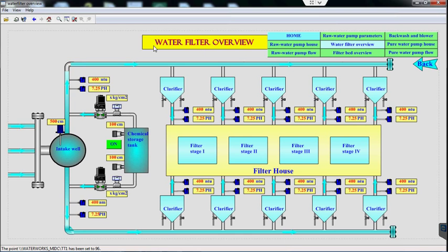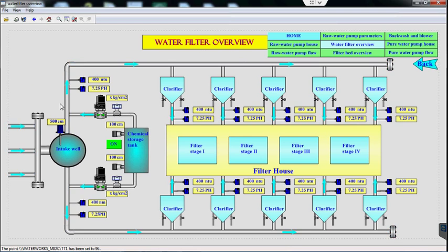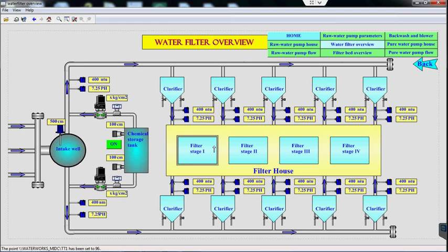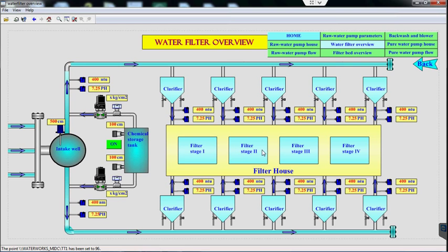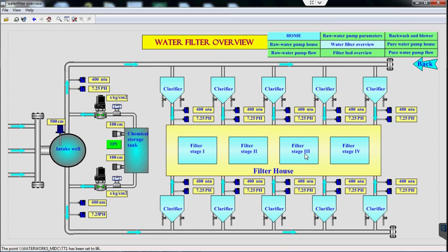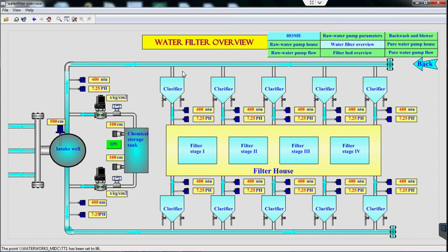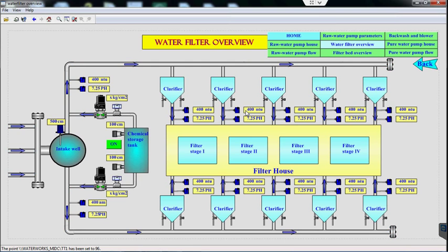Water filter overview. The filter house includes a water intake well and chemical dosing system, clarifier, and filter bed. There are four stages of filter house. Stage 1 has 18 filter beds, Stage 2 has 14 filter beds, Stage 3 has 6, and Stage 4 has 14. Water supplied from the raw water pump is collected at the intake well, from where it is distributed to each clarifier in two different streams or open channels. Turbidity and pH transmitters are provided on each channel to measure the turbidity and pH of the water.